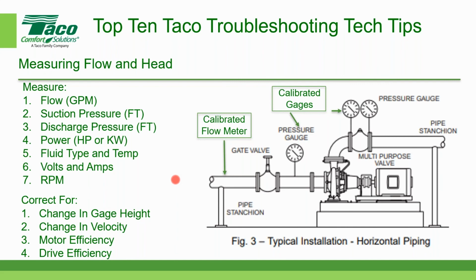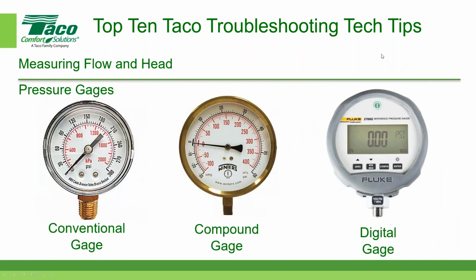You also need to have calibrated gauges. So this question comes up from time to time: how do I get a calibrated pressure gauge? Well, most suppliers can check the calibration before they ship the gauge to you. And I have a little photograph here of what the instrumentation looks like. Let's go over here for a second. So here's a conventional gauge on the left. I did want to point this out. This is a compound gauge in the center, and this is a digital gauge.